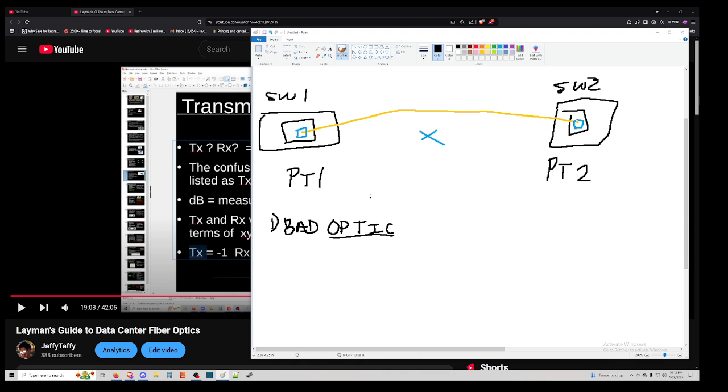They transceive or translate digital data into fiber optic light data that can be read and transmitted over the thousands of glass bristles that exist within a fiber. So that way they can go to another switch, which then gets translated from light to digital, and that generates a lot of heat. And that heat can result in optics going dead, or not being able to continue their function.